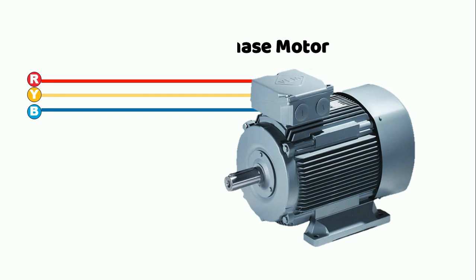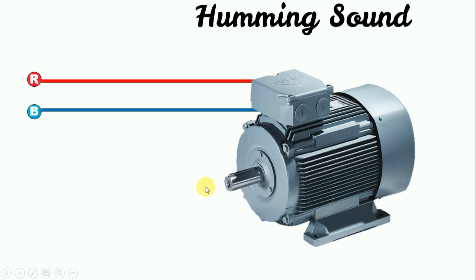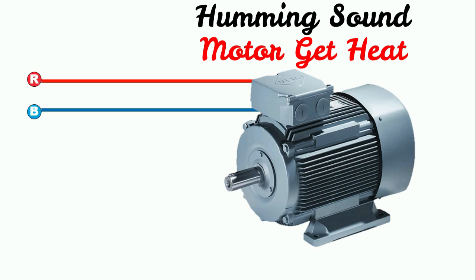If you have equipment which requires three-phase power supply to run — for example, a motor — this motor works on three-phase power supply. Now, if in running condition, power supply of one phase is gone, the motor won't stop. It will continue to work, but it starts making a humming sound and slowly starts heating up. After some time, the motor may get burned.